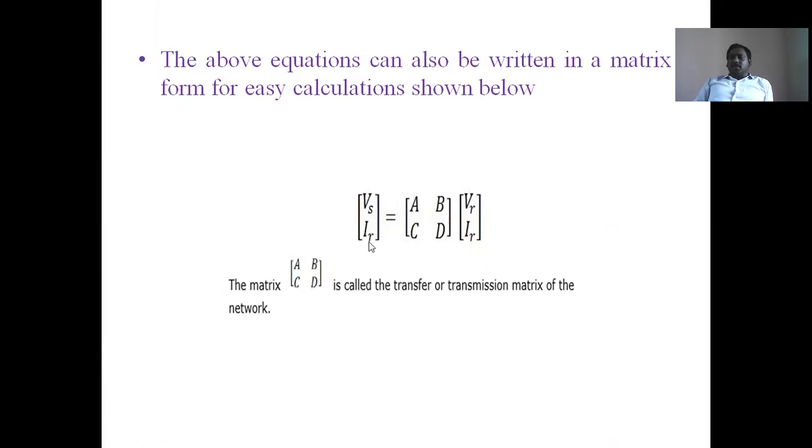If Vs and Is can be easily determined, then finally we determine the performance characteristics, such as percentage regulation, (Vs − Vr)/Vr × 100. Vs, Is, Vr and Ir can all be determined from ABCD parameters. Transmission efficiency is receiving end power, Vr·Ir·cos φr, divided by sending end power, Vs·Is·cos φs, that is output power by input power.